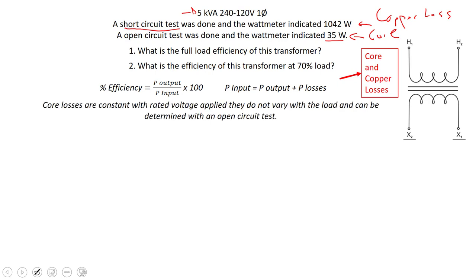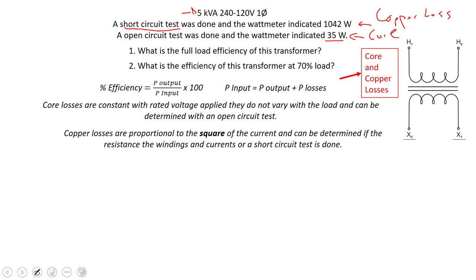Core losses are constant with rated voltage applied — they do not vary with the load and can be determined using the open circuit test. Copper losses, on the other hand, are proportional to the square of the current, and can be determined if the resistance of the windings and currents are known in both primary and secondary, or by doing a short circuit test for full load copper losses. Since P equals I squared R, if the current changes even a little, it has an exponential effect on the true power dissipated by each winding.